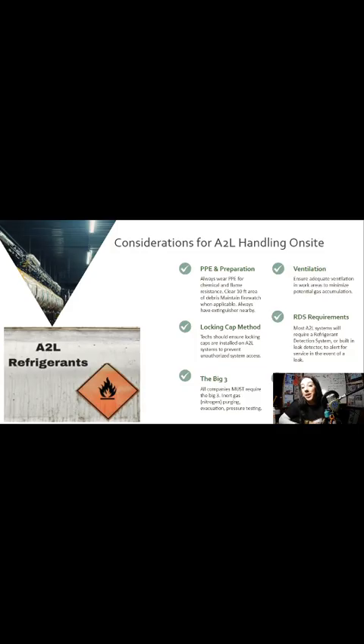Ventilation: ensure adequate ventilation in work areas to minimize potential gas accumulation. This isn't about toxicity—these refrigerants have very low toxicity, if any. It's because this stuff will only burn if you have a very large accumulation of gas in a small space; a little bit with a match 20 feet away won't ignite it. This will be code in every single city, code nationally, and it's a requirement from the manufacturer for all A2Ls. It's also a requirement of the AIM Act itself, so it is a national code.